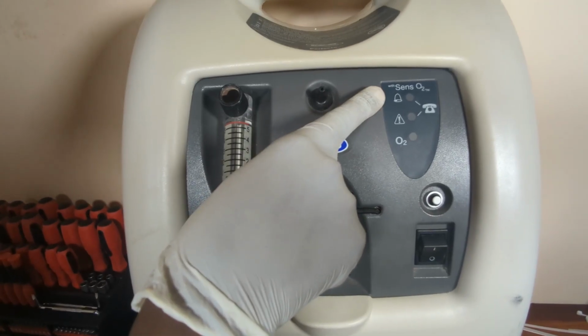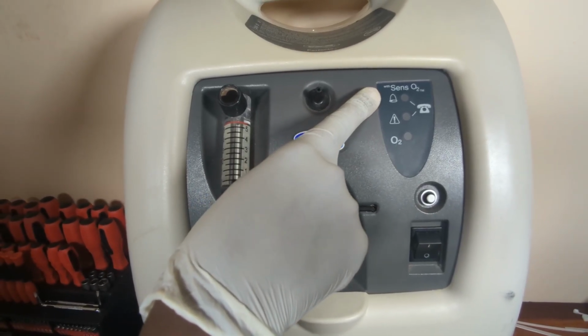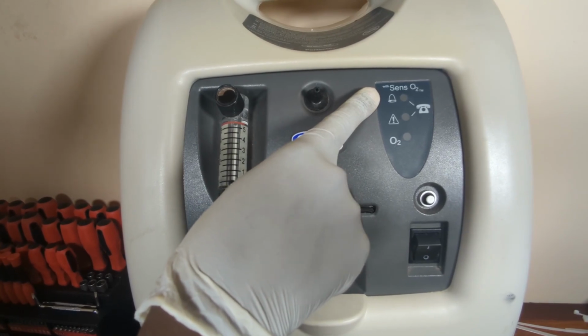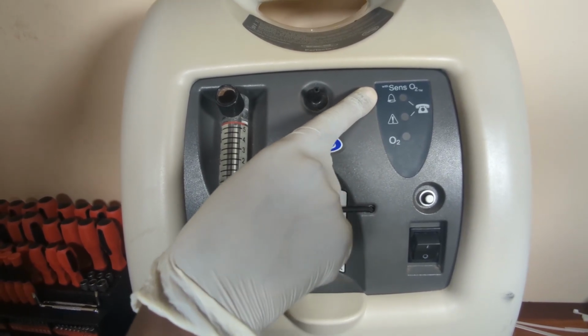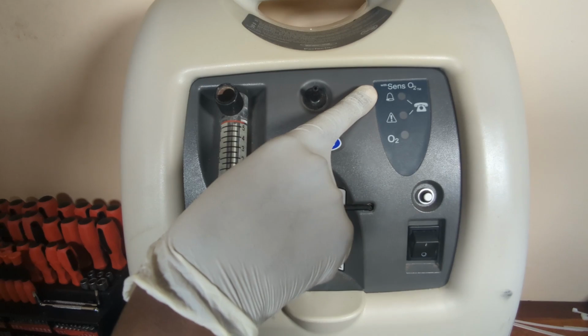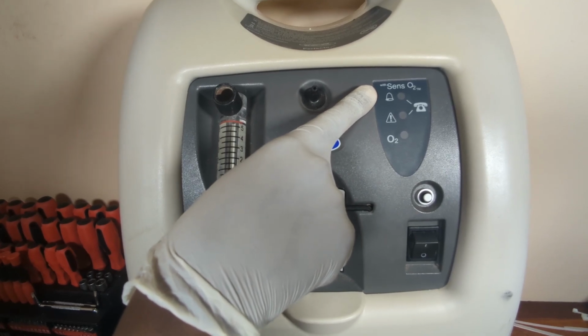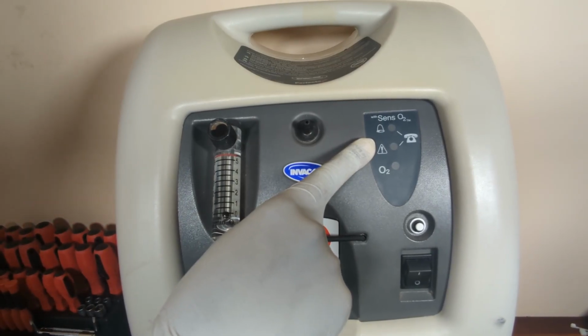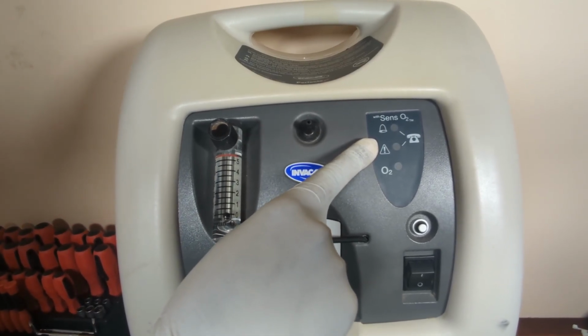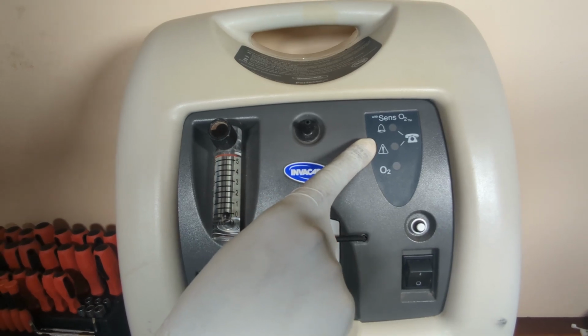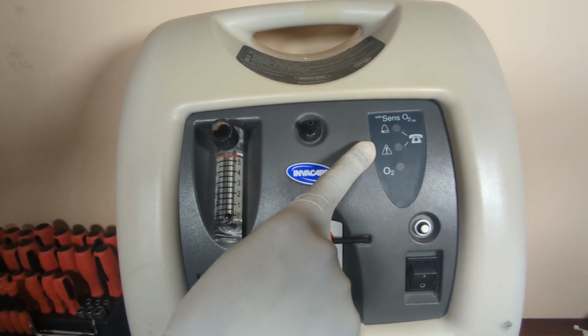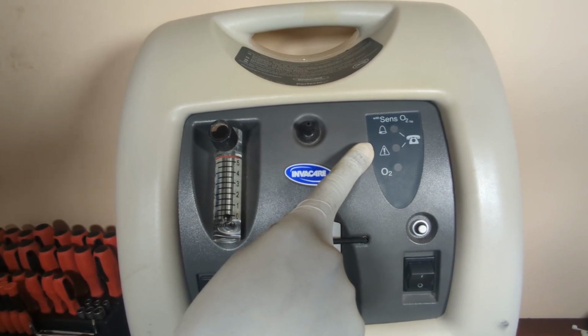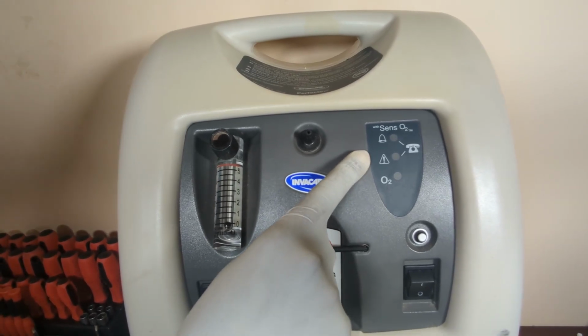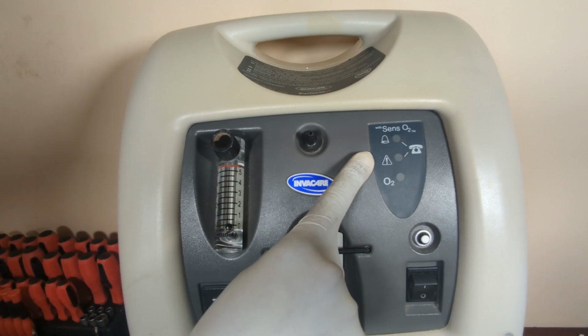The first LED with the bell icon indicates the system failure and it lights red. It is normally accompanied by an audible alarm when oxygen purity is below 73%. The second LED with triangle and exclamation mark icon indicates low oxygen concentration. It lights yellow when the oxygen concentration is between 73% and 85%. When there is a sensor failure, the yellow indicator flashes.